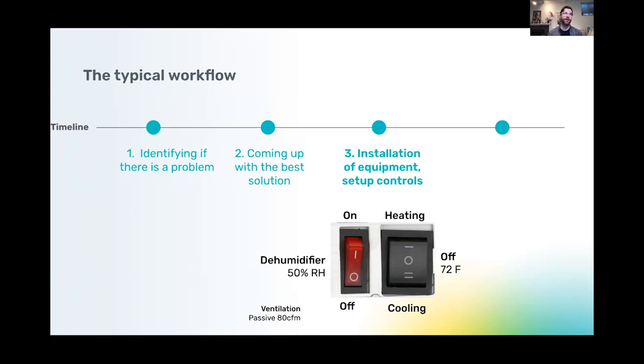What we see also is that there are ducts sweating. So the actual ductwork is dripping wet. And often the solution in heating and cooling, the technician comes, especially in a hot and humid environment, and they close the ventilation. They close the damper, they shut it. They say, this will solve your problem. Sometimes when you don't know a proper solution, shutting off ventilation, keeping that high humidity outside of the home ends up being the go-to when there's an issue. And of course, we often see heating and cooling equipment is oversized, meaning there's going to be low runtime, and there's going to be indoor air quality issues, and there's going to be comfort issues as a result. So there are many opportunities to make a situation worse rather than fixing it.